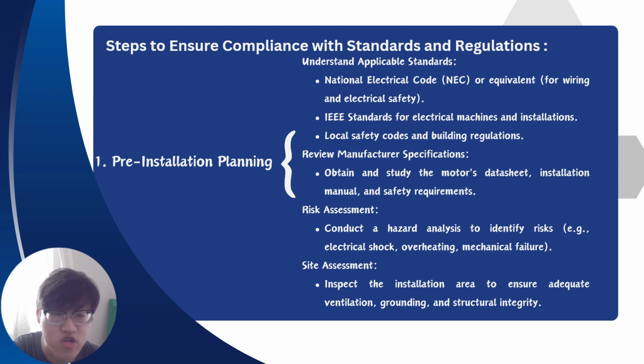Next, review manufacturer specifications. Obtain and study the motor's datasheet, installation manual, and safety requirements. This means that different methods or different constructions have different specifications, and the engineer needs to obtain the motor's datasheet. Next is a risk assessment, which is to conduct a hazard analysis to identify risks, for example electrical short, overheating, mechanical failure, or short circuit. Next is site assessment. It inspects the installation area to ensure adequate ventilation, grounding, and structural integrity.